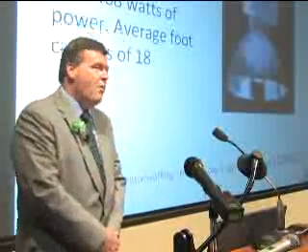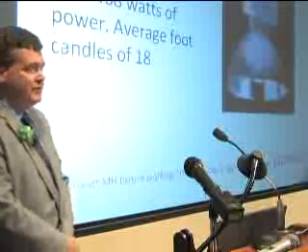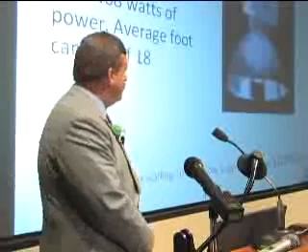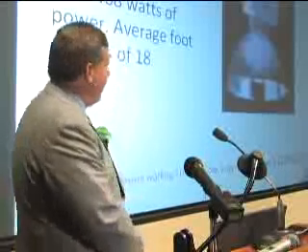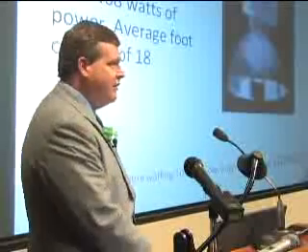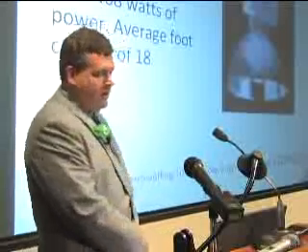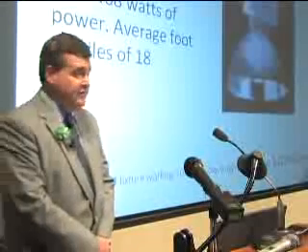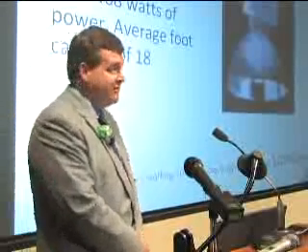This is called a 400-watt metal halide, which uses 468 watts of power. An average foot candle reading is about 18 with a 400-watt metal halide, and that's a measurement taken at about eye level. So one 400-watt metal halide fixture that works 10 hours a day, 5 days a week, costs $127 a year to operate.